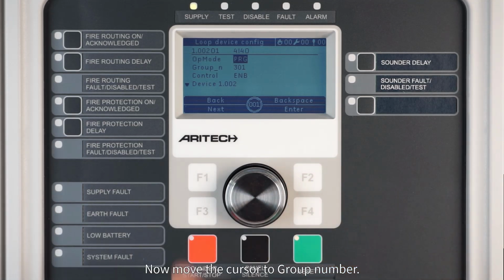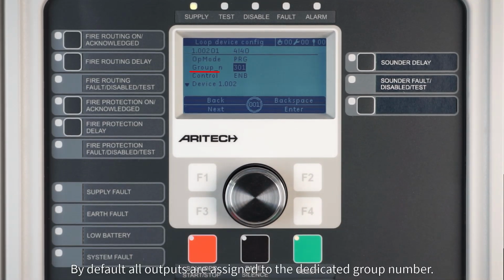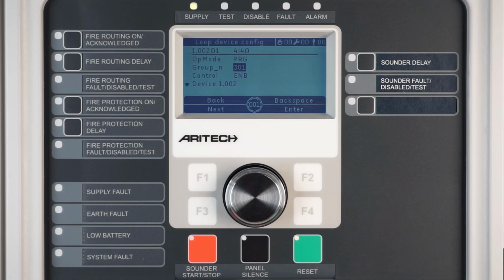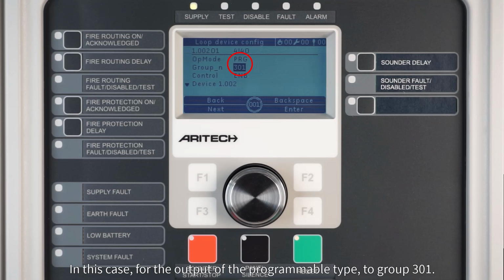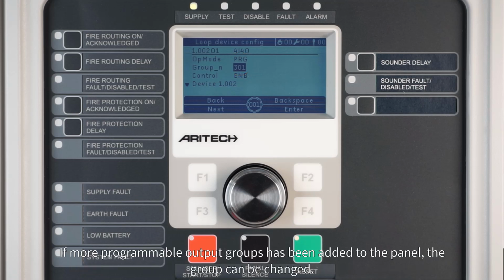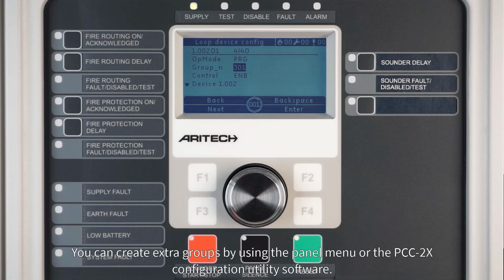Now move the cursor to group number. By default, all outputs are assigned to the dedicated group number, in this case, for the output of the programmable type, to group 301. If more programmable output groups have been added to the panel, the group can be changed. You can create extra groups by using the panel menu, or the PCC2X configuration utility software.